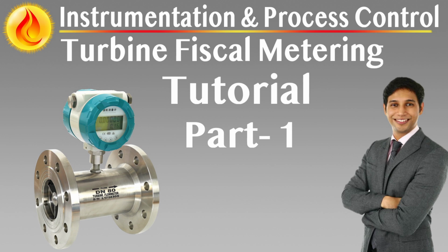Meter prover integration. The proving system, bidirectional or compact, must comply with API MPMS Chapter 4 and be space optimized for offshore installations if applicable. The system includes dual redundant detectors, precision pulse counters, and interfaces for proving sequence automation. The prover must ensure 10,000 pulses per calibration run and a detector resolution matching this precision. Integration with the microcomputer architecture allows automated validation sequences with fail-safe abort logic for out-of-limit deviations. Sphere velocity, impact attenuation, and detector redundancy ensure repeatability without measurement bias or mechanical fatigue.